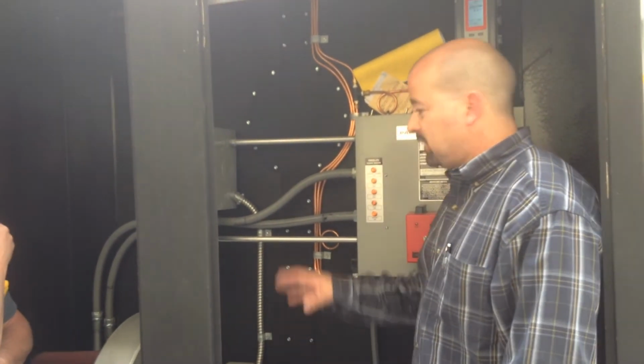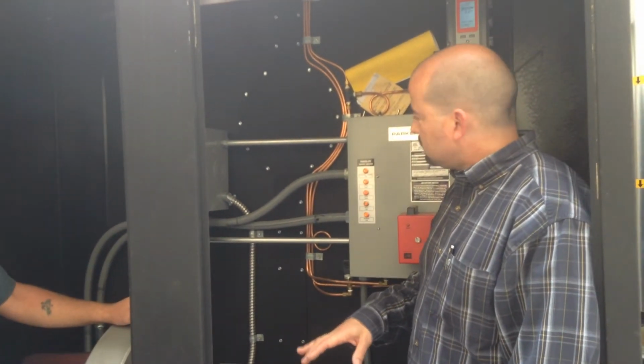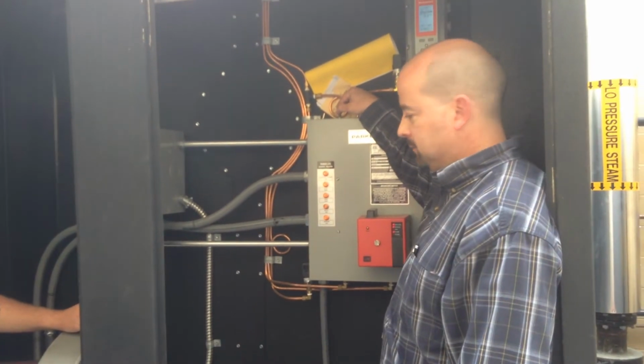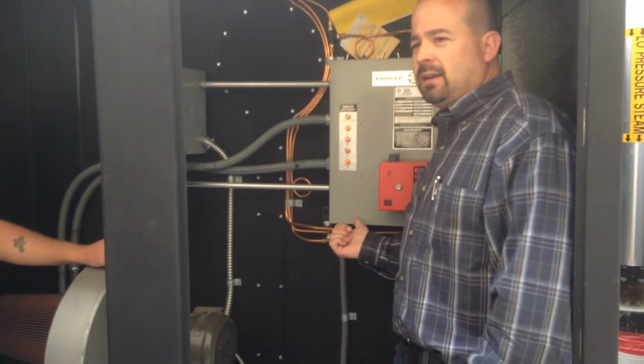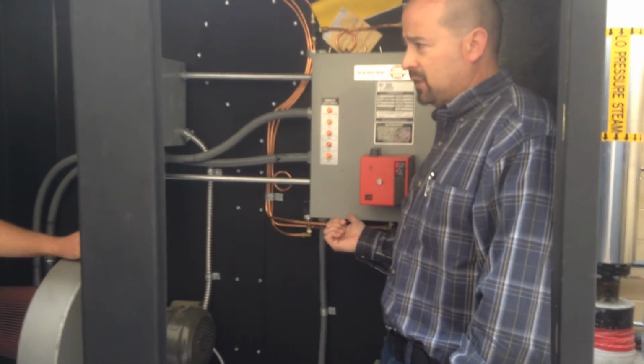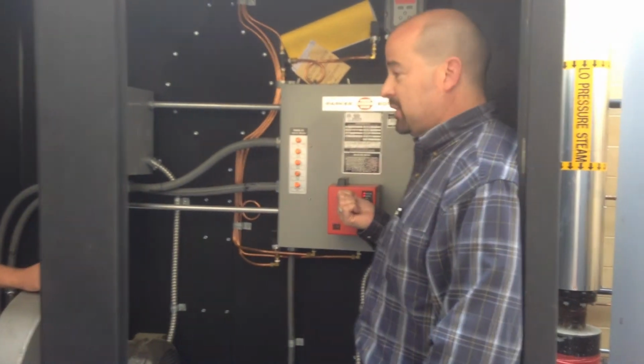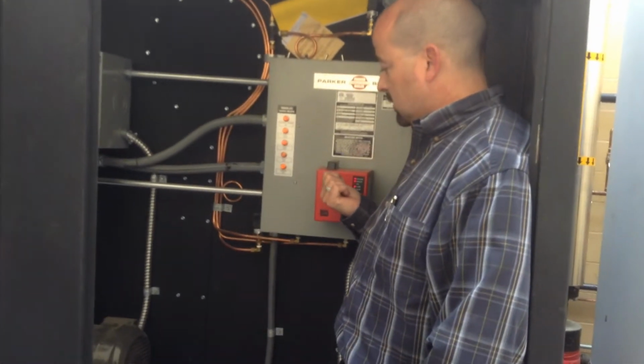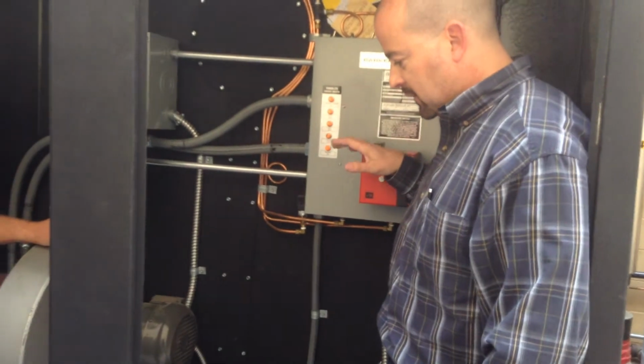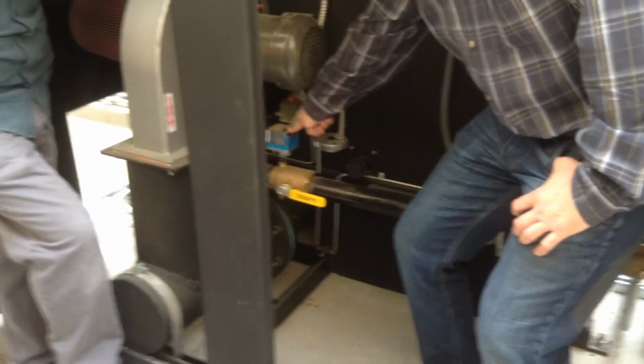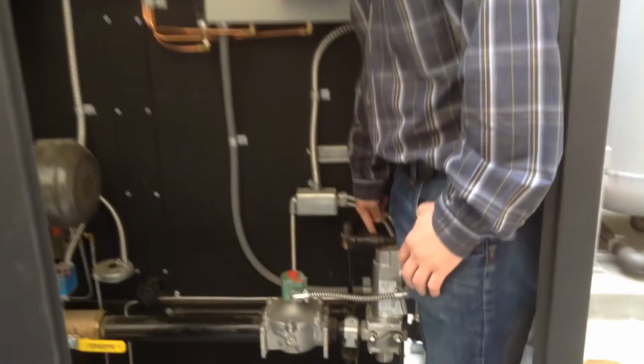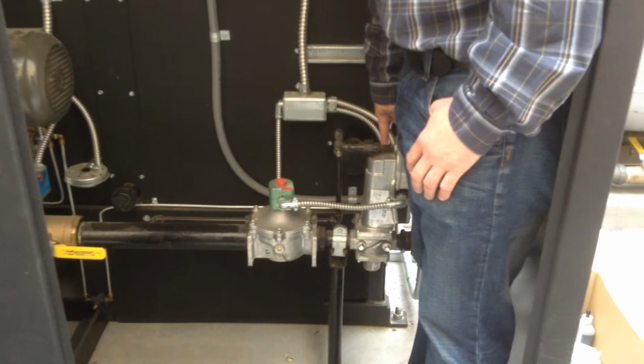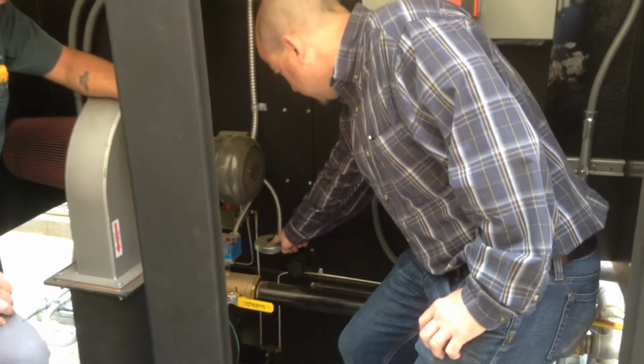Okay, let's talk about manual resets. I mentioned this one. I mentioned the one inside, the manual reset high limit if the steam pressure gets too high. I mentioned the flame safeguard, the brains of the flame circuitry. You've got a gas pressure switch here. It's labeled. It's a high gas pressure switch. You've got a low gas pressure switch, which you can't see because it's behind this valve. You've got a flame rollout switch, which is this one right here.